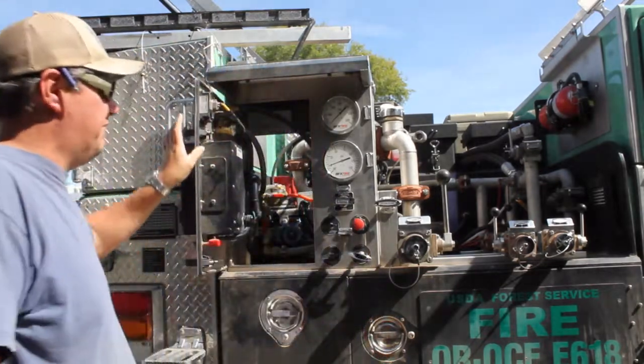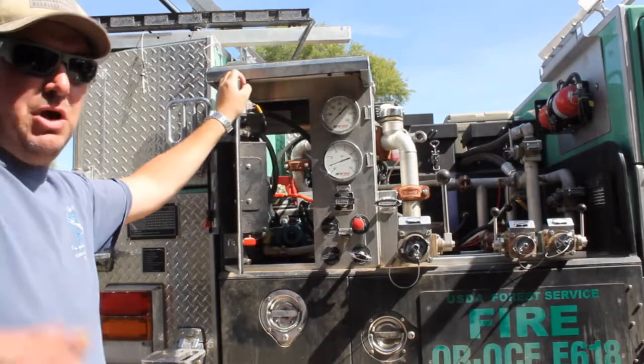The instructions on the inside are just for flushing — we'll deal with flushing later. So if we need to make foam, we got to make sure our return valve — that lever right there — is open. Our supply valve is open. Then I come in here and make sure I am on foam inject on the bottom three-way and tank return on the top three-way. That should be able to sit as-is all the time.